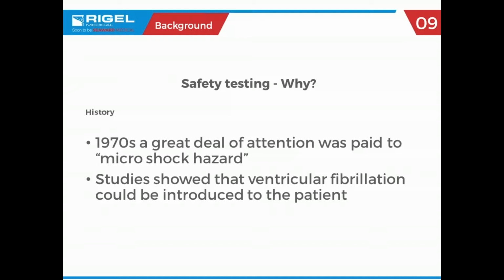So a little history lesson here. Back in the 70s, his name will pop up on the next slide, a guy by the name of Ralph Nader went into a hospital and discovered that there were some electrical safety issues, shall we say, and kind of wrote an exposé. Ralph Nader is a political advocate. So he wrote an article about microshock hazards. If there's enough current flow, and it's surprising, we'll have a chart as to what level of current can start to cause the heart to go into a resonance, particularly fibrillation. It doesn't take a whole lot of current for that to happen. And unless you fix it pretty quick, you lose the patient.